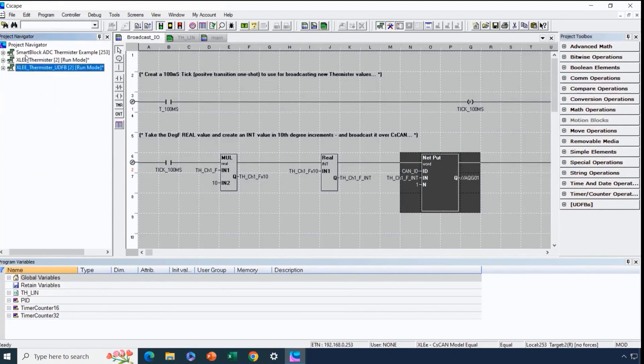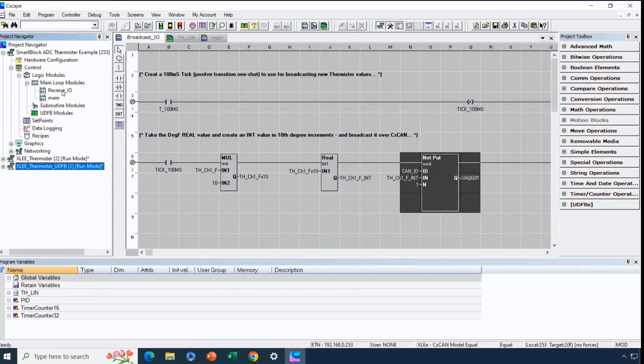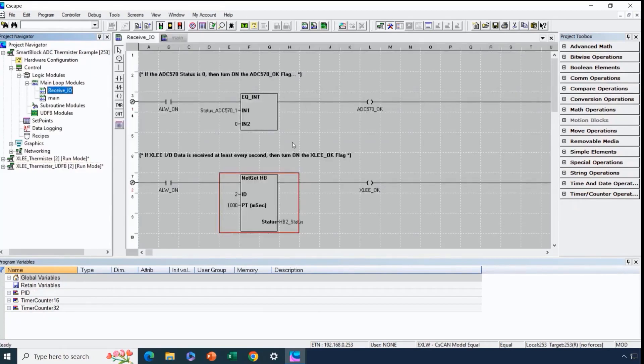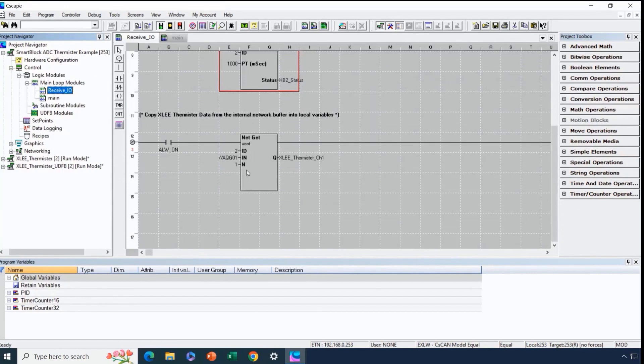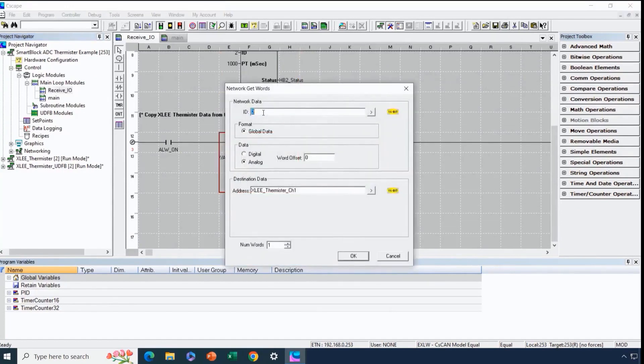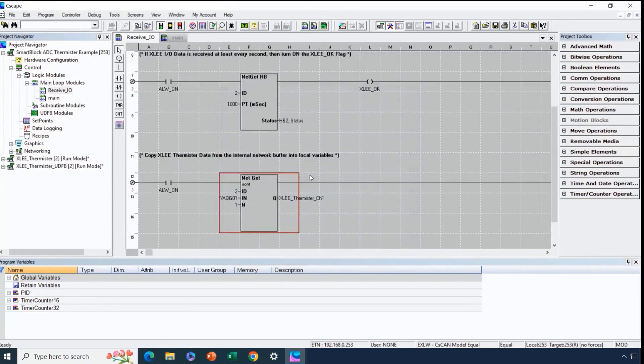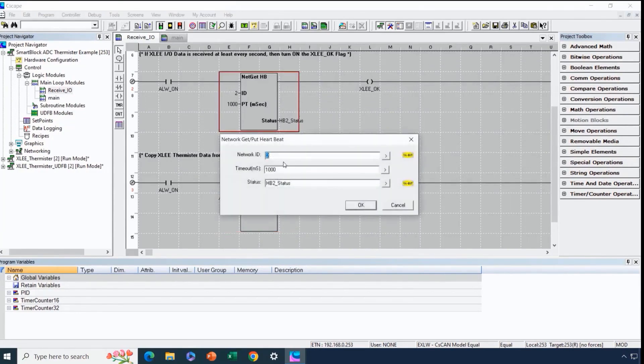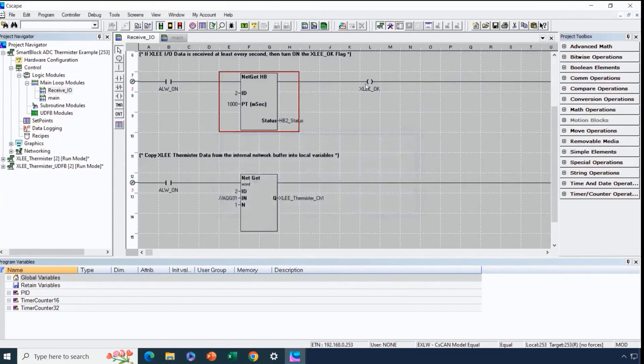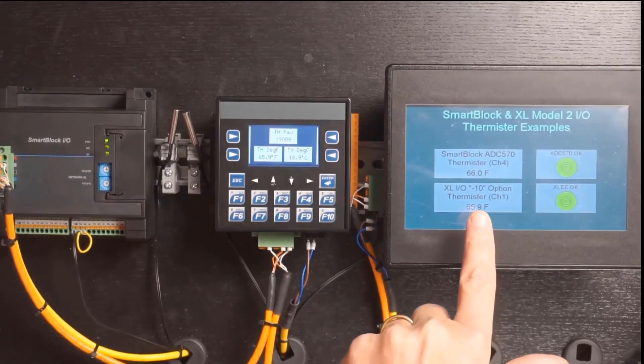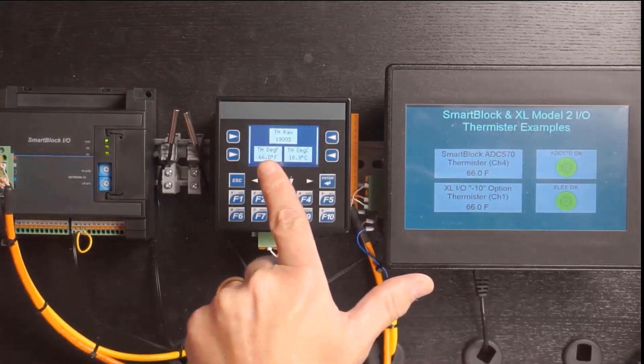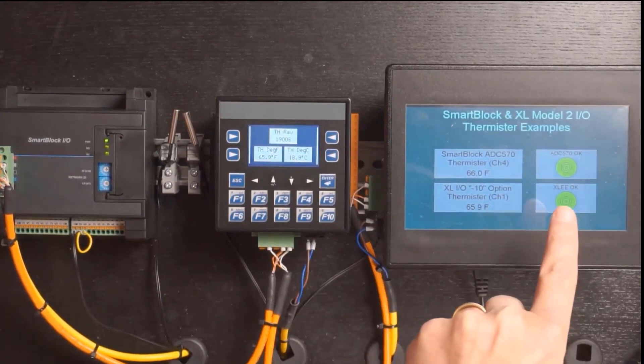Now we'll look at how it's received by the EXLW. In the ReceiveIO section of that program, we use a netget function to retrieve data broadcast by network ID 2, which is the XLE. It comes from the analog data from the XLE with no offset, and we copy it locally into a local variable. We also created an OK bit for the data coming in from the XLE, so that if the XLE stops communicating for more than a second, we can turn off the coil. Here we can see the value coming in from the XLE — 65.9 or 66 degrees Fahrenheit — and we can also see the OK LED.